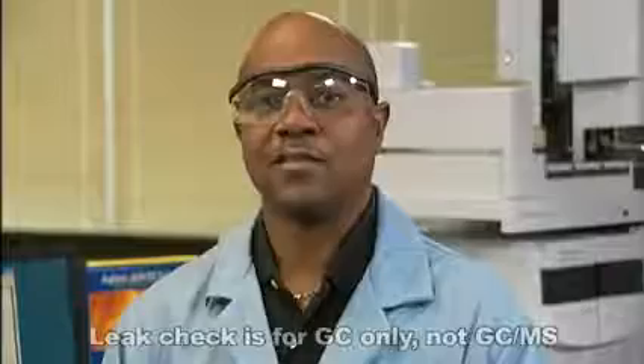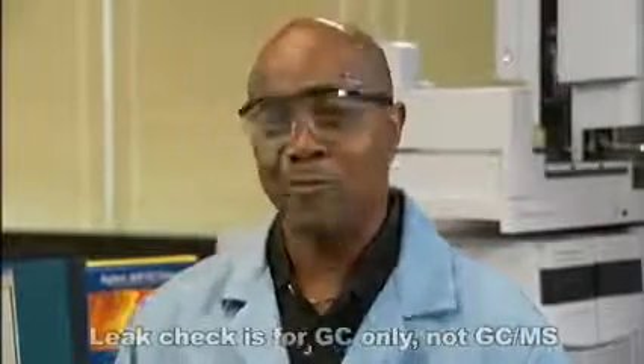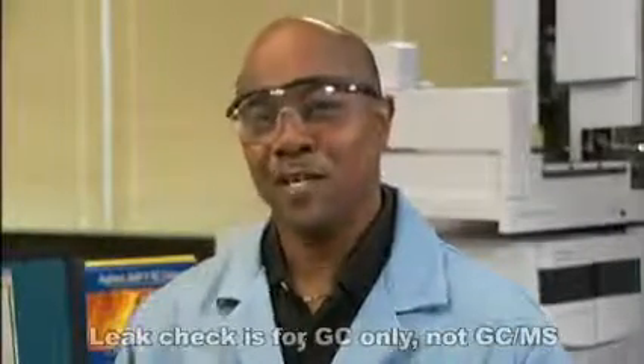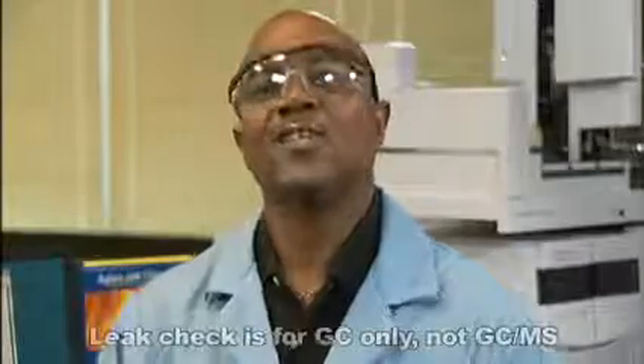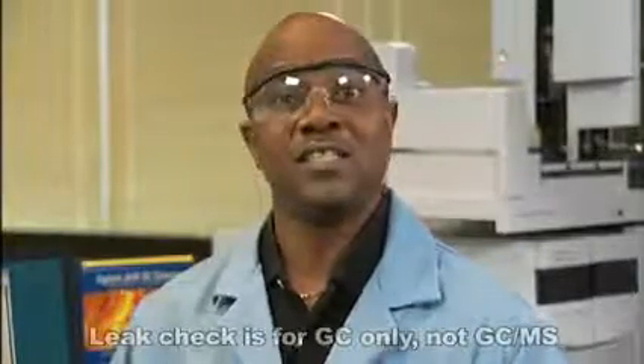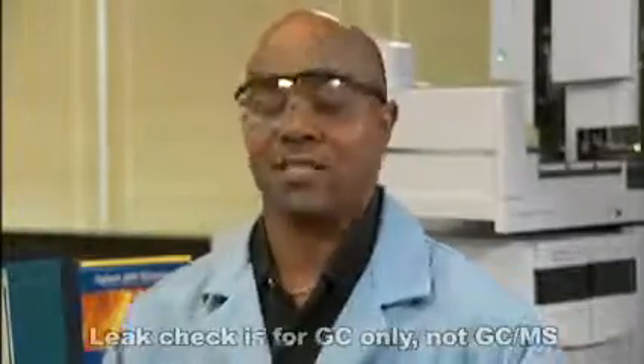Oh, one more thing. What we did was the manual way to run the test. If you're lucky enough to be using LabAdvisor, you could select the appropriate GC and run the prep run leak check. If you see a problem, you'll want to replace the line. Now, of course, there could be other reasons for retention shifts.